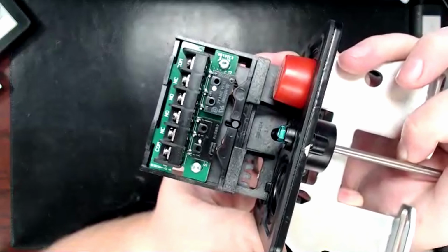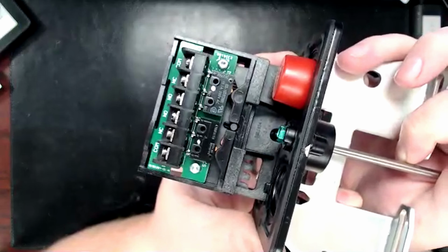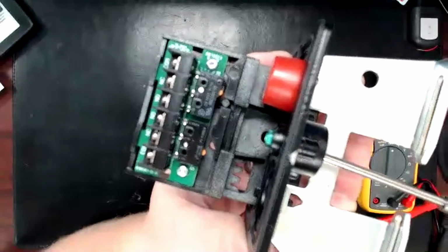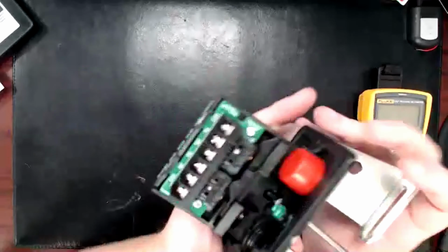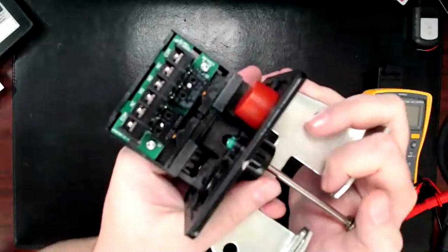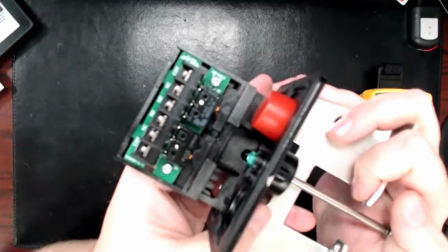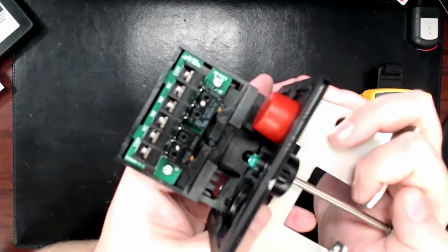And then as you start to close the valve, it slides it over and releases it, and that's when it changes state. But if you notice, when there's no pressure put on this at all, that switch is also left in its not resting state. That can sometimes cause some problems if it's not set up properly. I've had them set up before where they were set just like this, where it's about to push the switch, and then you get going and it makes it change condition, and then you get the valve all the way closed and it goes back to how it was before. And that's not how it's supposed to be.